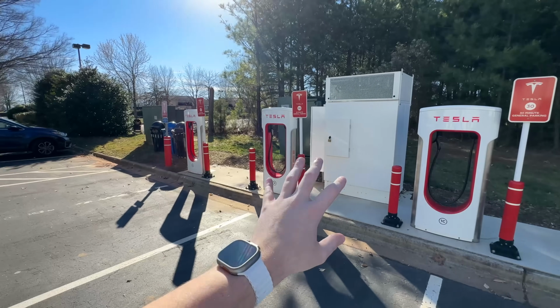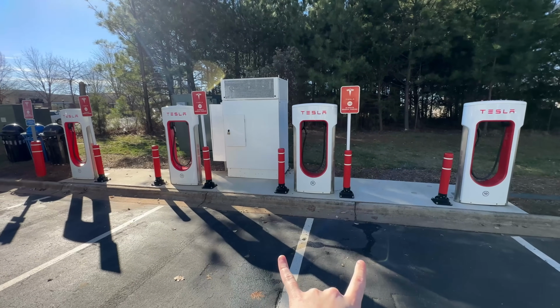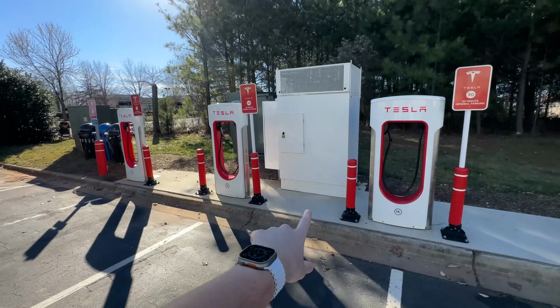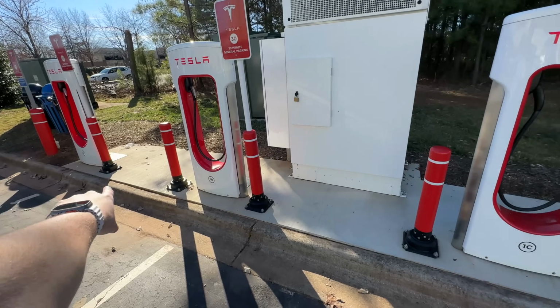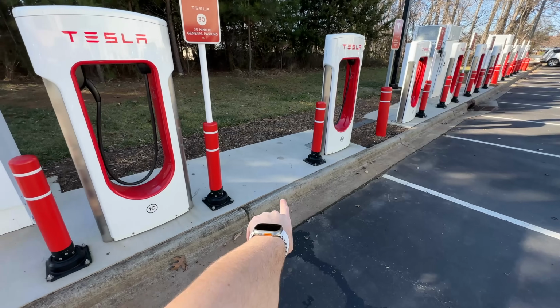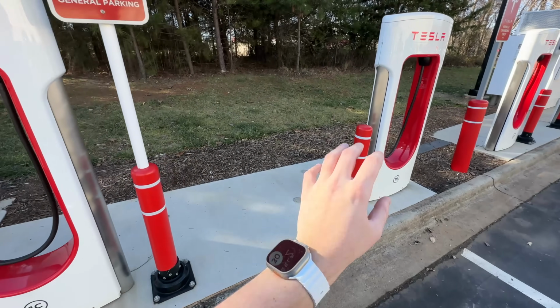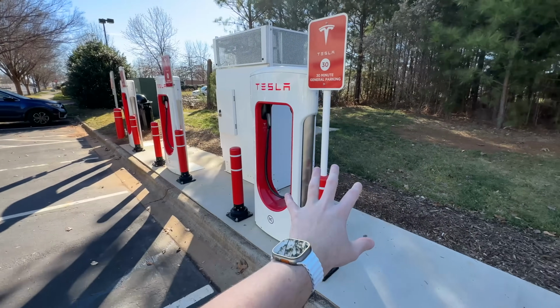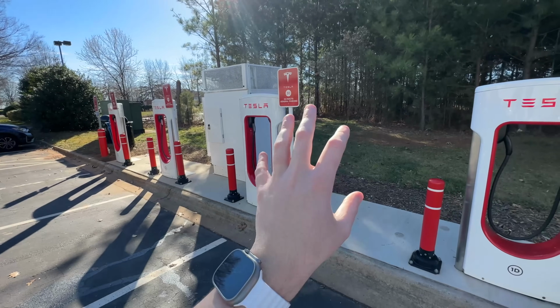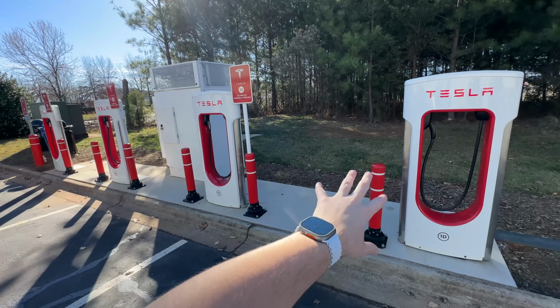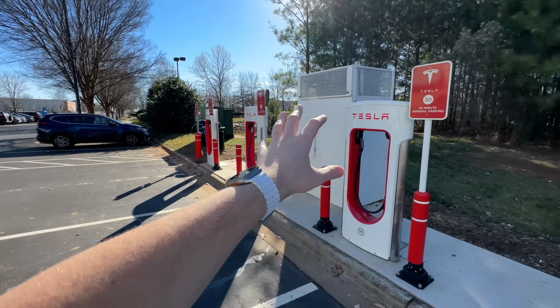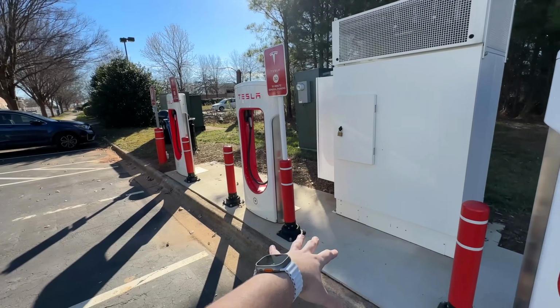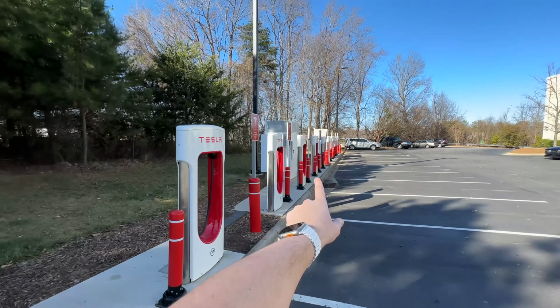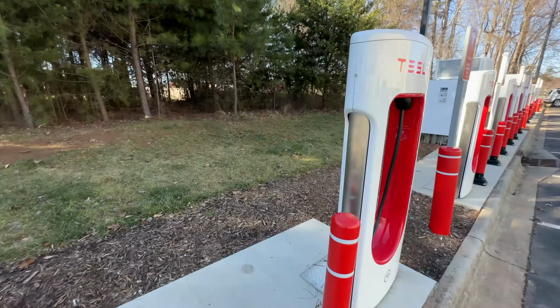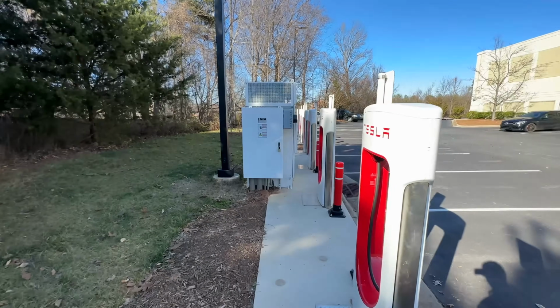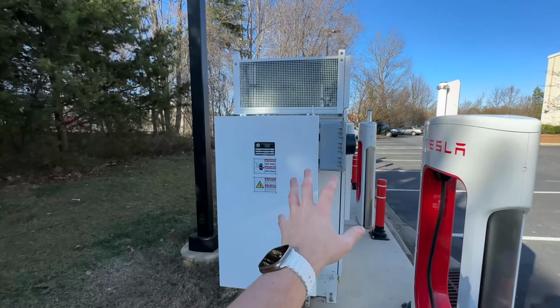But what we're talking about specifically today is these prefabricated supercharger units. If you notice here, you have the cabinet and all these posts on one piece of concrete. This was not made here on site—it was shipped in on a truck and craned in, allowing for much faster installation, and having this entire unit as a UL listed or NRTL evaluated unit. You have all the conduits in there, wireways for the DC buses, and an integrated mini switchgear of sorts on the side of it. So let me show you the entire power flow.